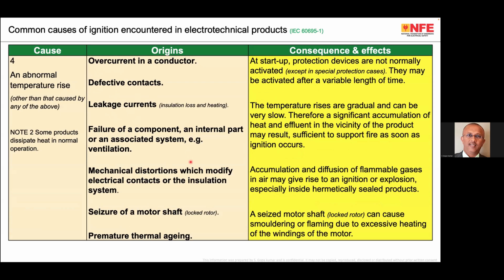So basically, with respect to fire from an electrotechnical product, such as some appliance which we are using in our house or some equipment which we are using in our industry, the reasons are very much identified. It is a mandatory requirement that the safety measure has to be built into this particular equipment. For example, for automatic disconnection, there can be a fuse. If there is no internal fuse, then the manufacturer will tell you very clearly that fuses must be provided externally. Example, a motor: the overload relay and the short circuit protections are sometimes made external because there is no internal protective measure. So depending upon the equipment, these measures are implemented.